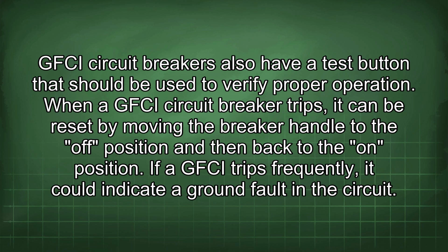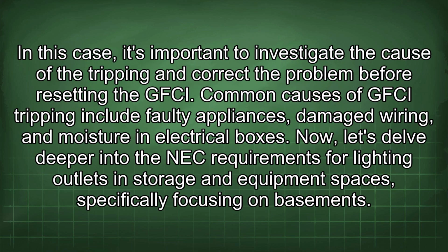If a GFCI trips frequently, it could indicate a ground fault in the circuit. In this case, it's important to investigate the cause of the tripping and correct the problem before resetting the GFCI. Common causes of GFCI tripping include faulty appliances, damaged wiring, and moisture in electrical boxes.